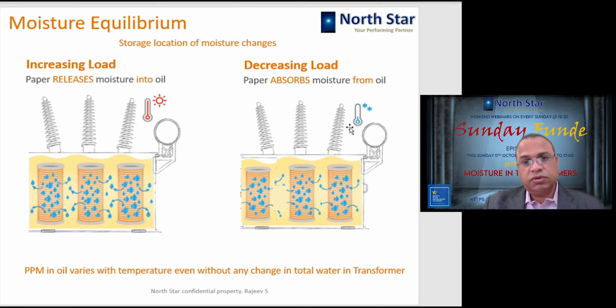On the contrary, when the load goes down or when night sets in and the temperature is low, the moisture is transferred from oil to paper. So the paper attracts the moisture back into it. This transfer of moisture from paper to oil and oil to paper keeps happening throughout the transformer's functioning. Even if the load is constant, it keeps happening because of ambient temperature variation. So if we are measuring the ppm inside the oil, it has very little significance, because that does not give you the true picture of the moisture content in the transformer. That is what I have said here: ppm in oil varies with temperature even without any change in total water in the transformer.